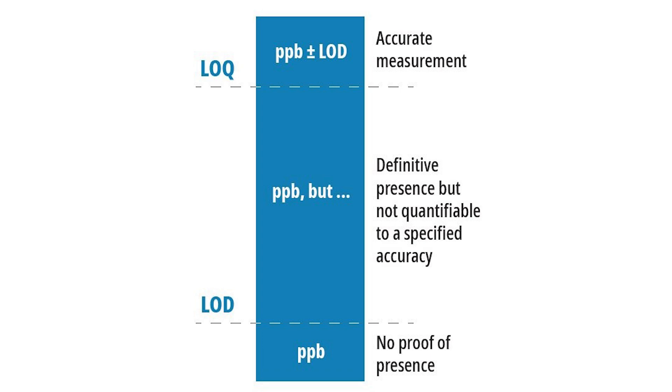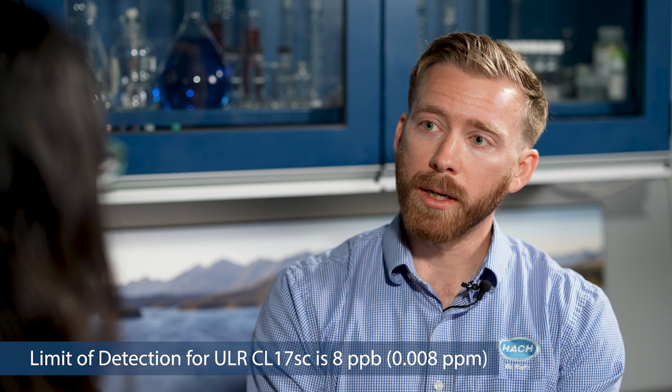When we think about dechlorination and ultra-low range chlorine measurement, this is really important for two reasons. One is for customers trying to completely remove chlorine from the system, the LOD is a really important number. The lower that limit of detection is, the closer you can come with confidence that your chlorine — or absence of chlorine — is below that number. So if your limit of detection is 8 and you're measuring 0, you're confident that your chlorine concentration is below that.